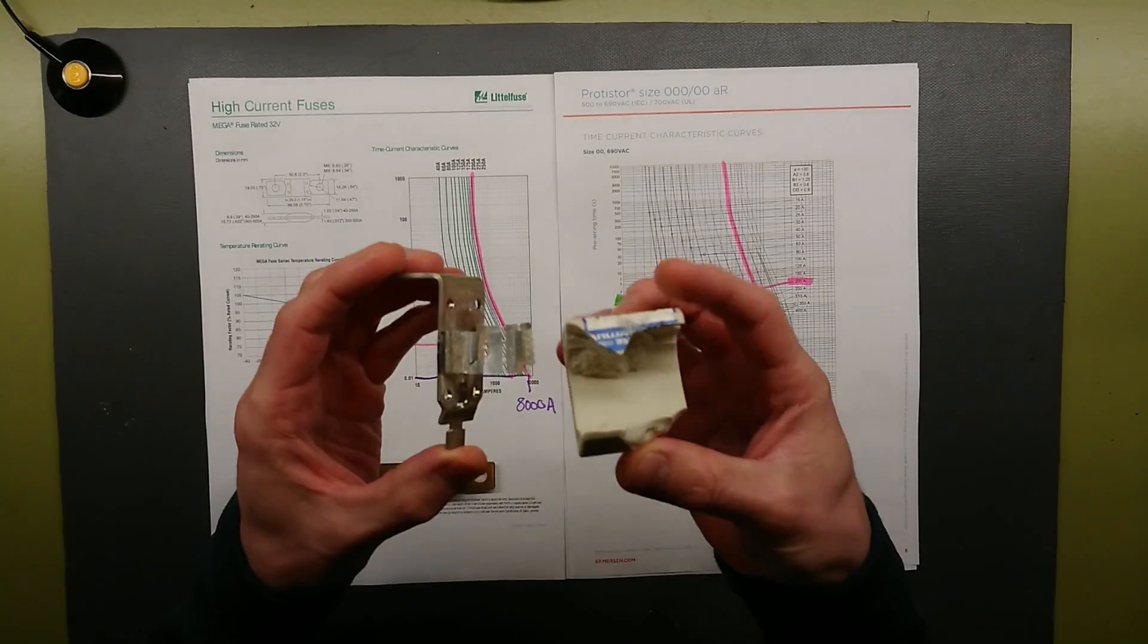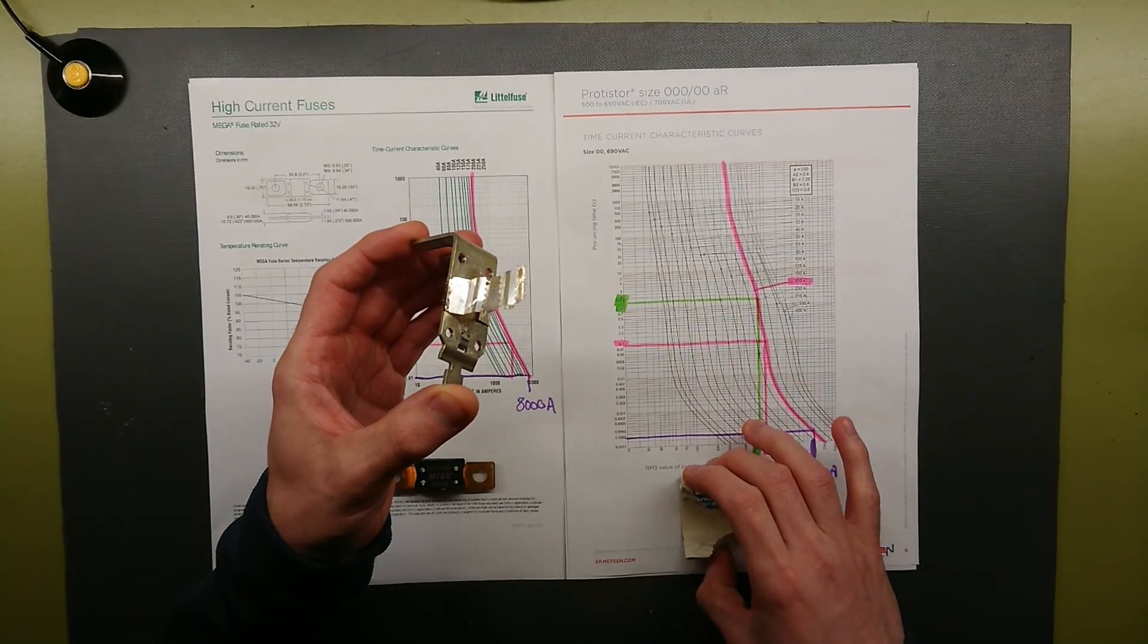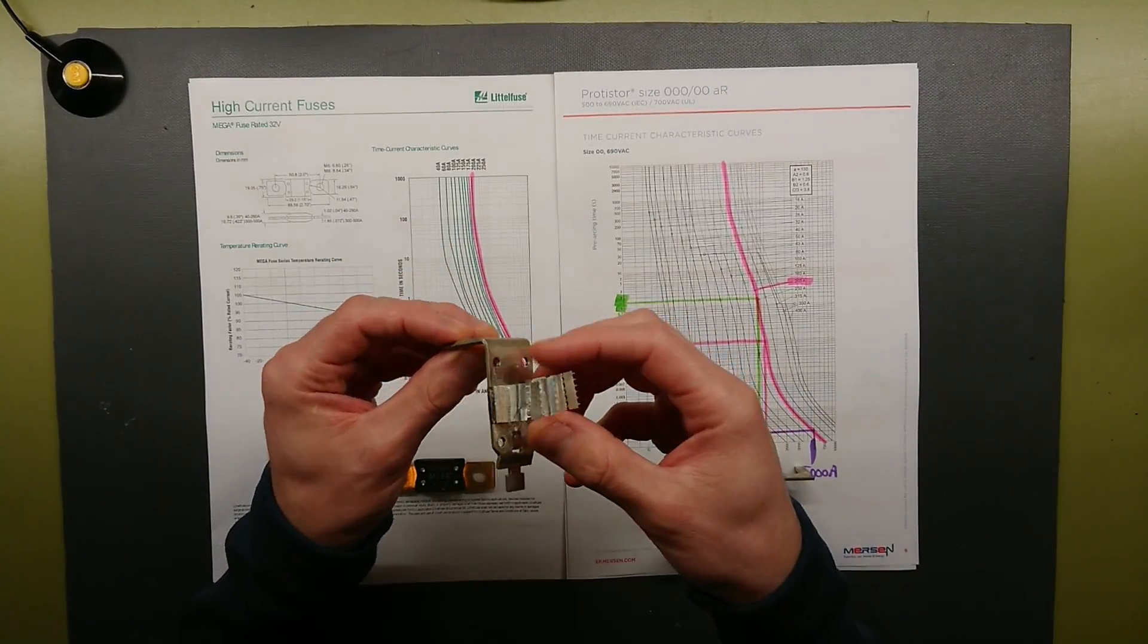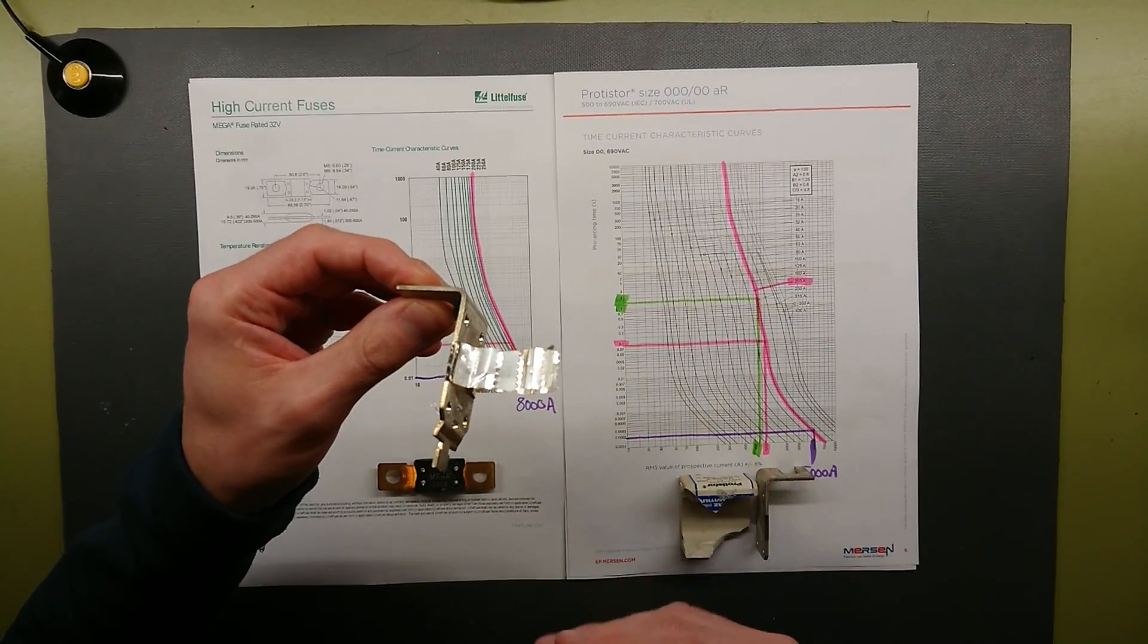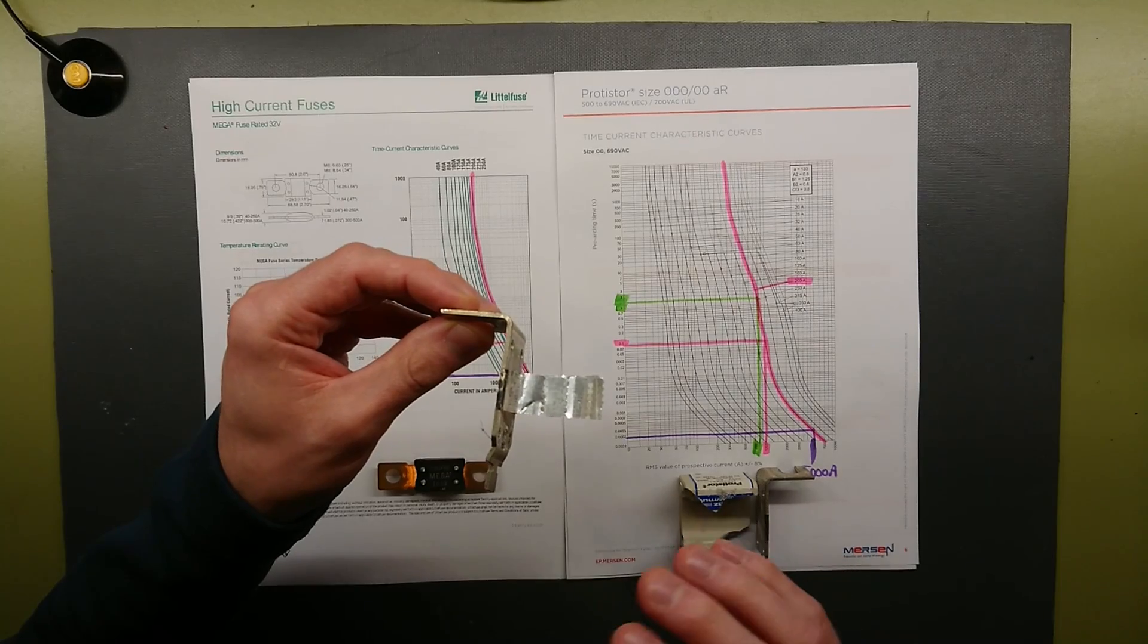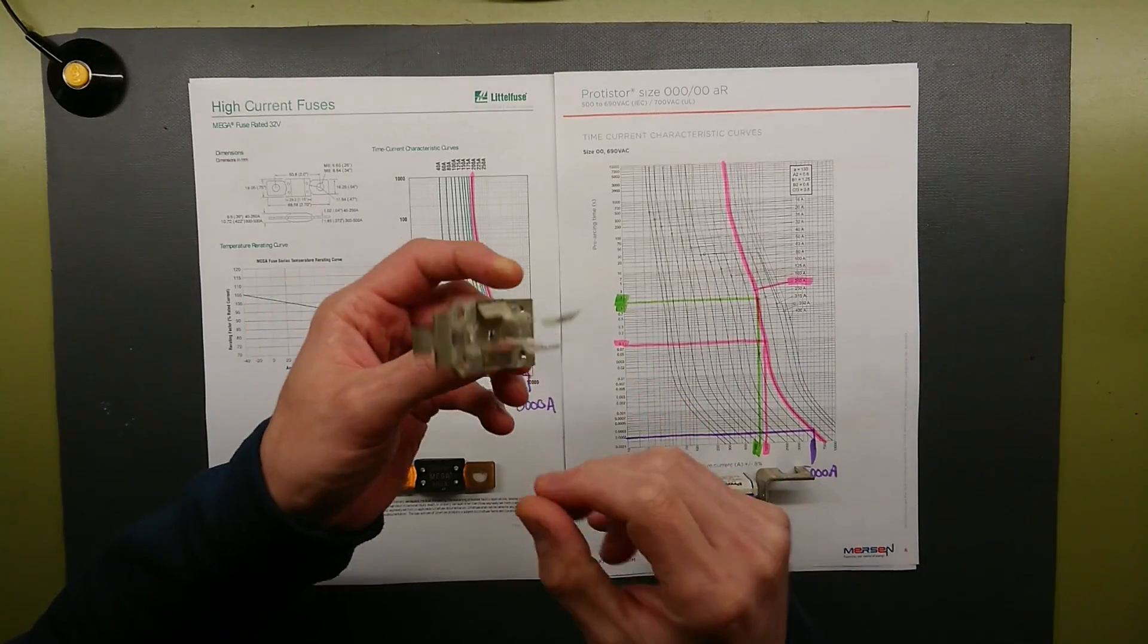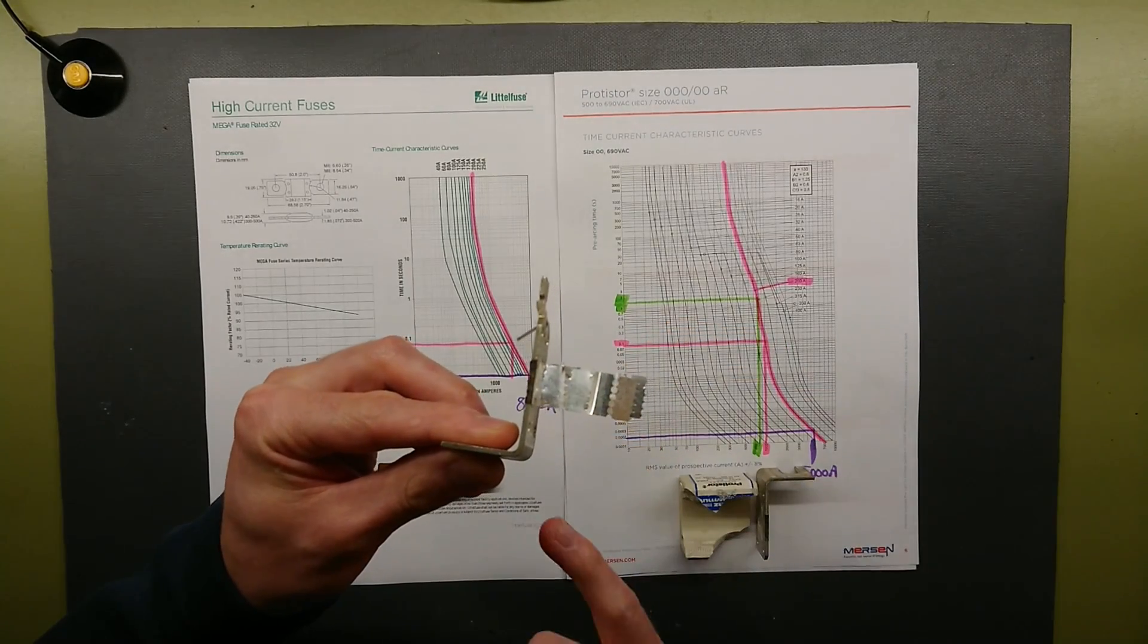It sits in a sand filled ceramic housing. This is because of the 41 watt dissipation. This fuse runs very hot when in use. Because to be fast acting, it will have to run just on the brink of melting. These are silver links, and as you can see this is perforated a lot of places.